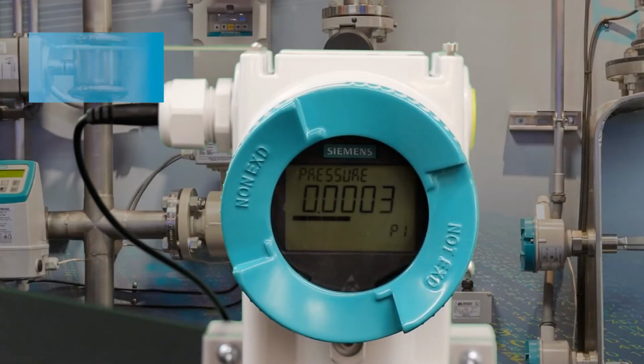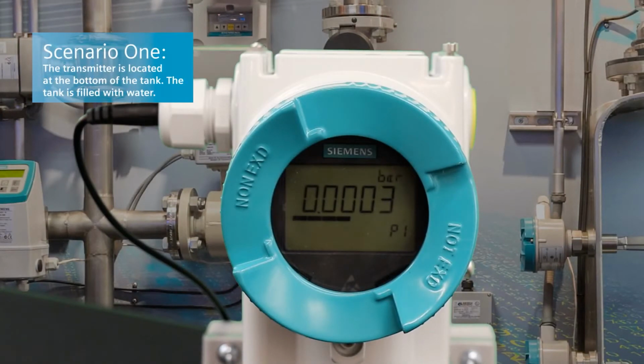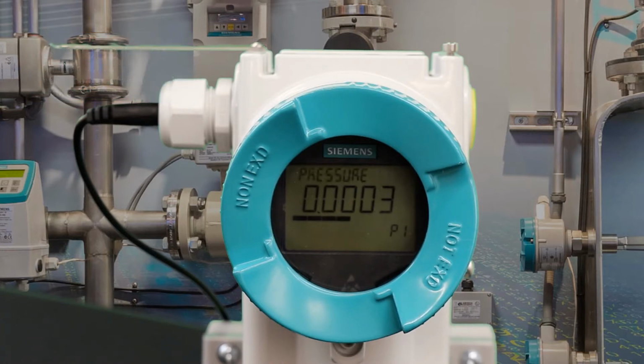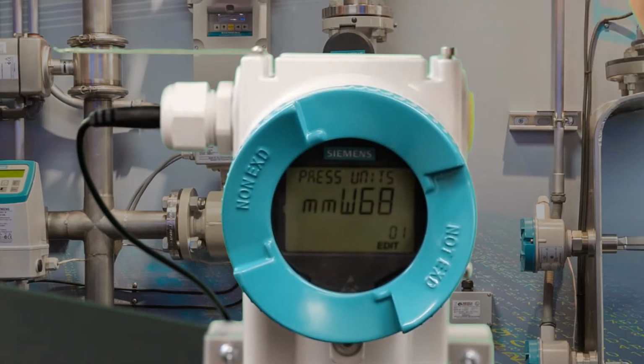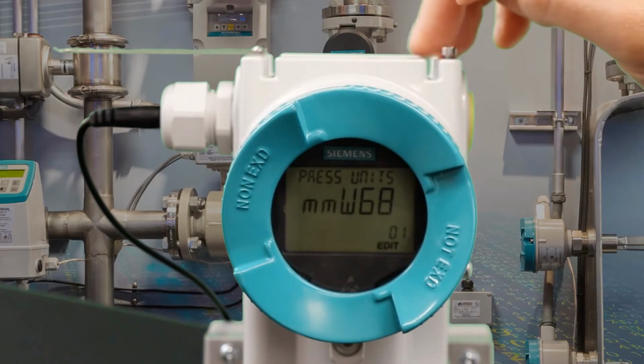In this application, the pressure transmitter is located exactly at the bottom of a 20-foot tank filled with water, and that tank is vented to the atmosphere. What we need to do is to configure 2 things. One is the pressure range, which is the lower range value and the upper range value, and also we need to configure the display. Later on, you will see why we need to configure the display independently from the pressure range.